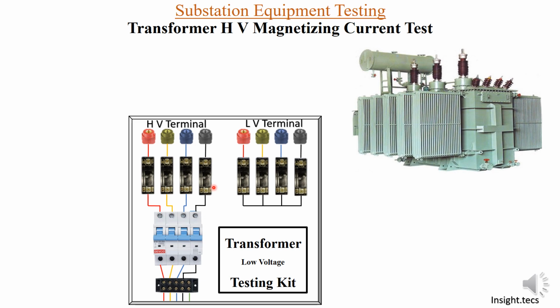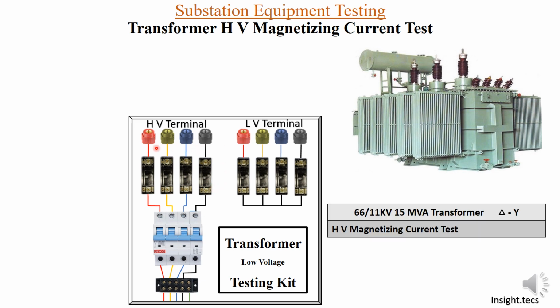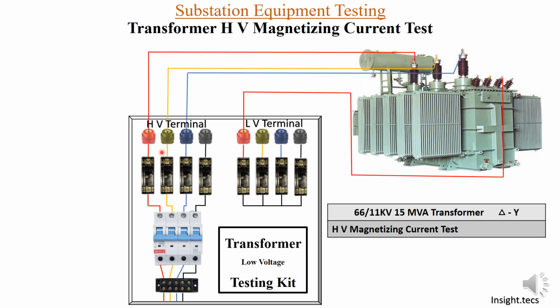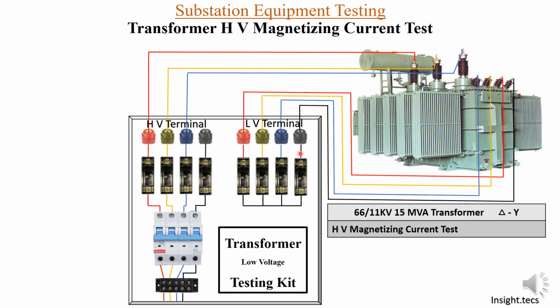First we have to connect the HV terminals to the transformer. The transformer on which we are going to perform the test today is a 66 by 11 kV 15 MVA transformer, delta and star winding. As it is delta connected, we will not have neutral on the HV side. Now let us make connections from the testing kit to the transformer. We will connect R phase, Y phase, B phase, and for the LV terminals we will connect R, Y, B and neutral, but we will keep this side open, that is, we will not close the fuse.